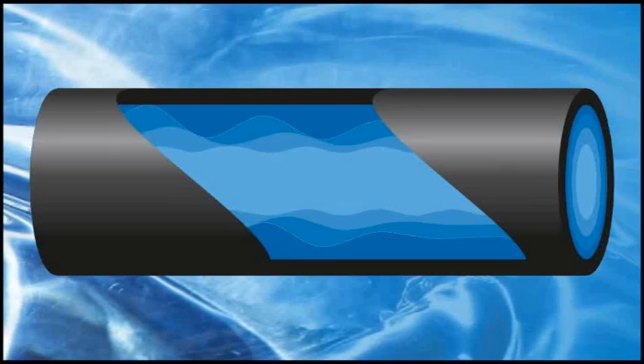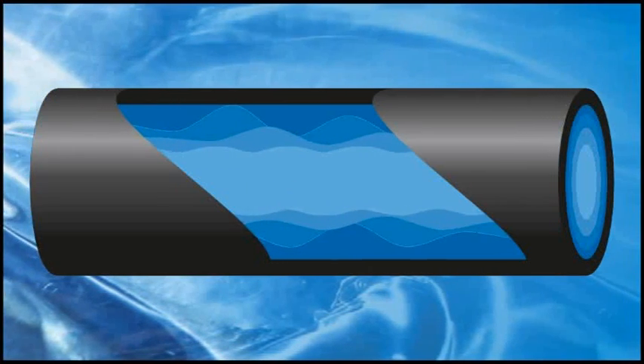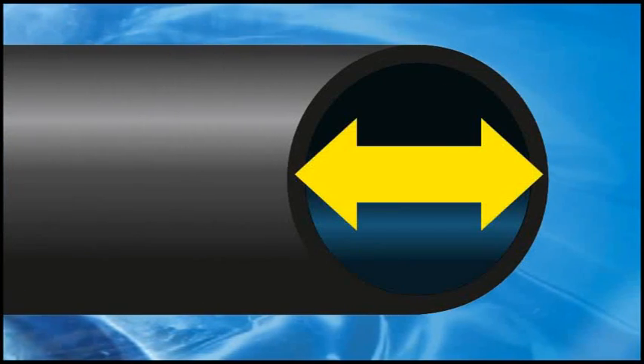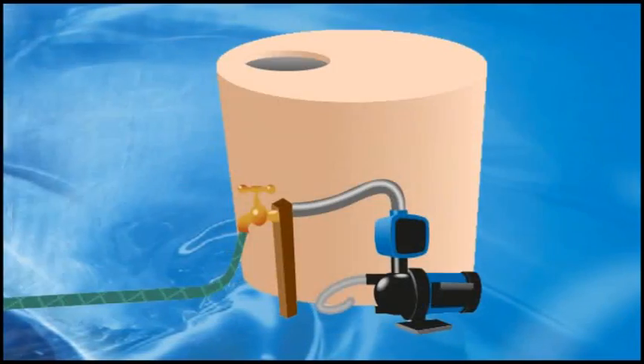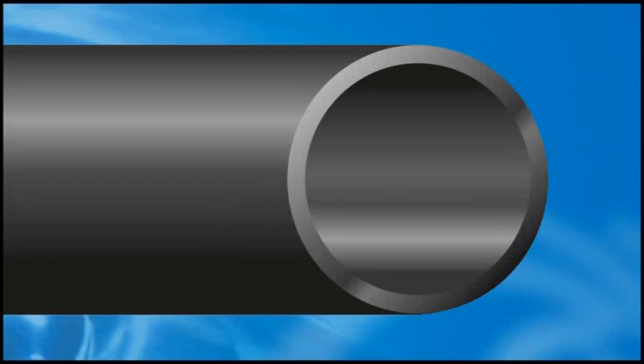Friction loss describes the pressure used to push water through pipes. The speed of the water travelling through the pipe, the diameter of the pipe, and the distance the water is travelling are all contributing factors in working out how much pressure is needed to do the job.